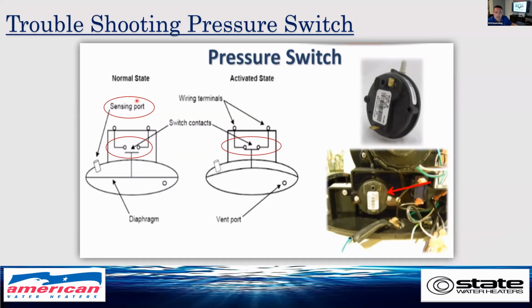So looking at this diagram, the sensing port is where the vacuum from our blower is coming and plugging into it. In a normal state, our diaphragm is flat, pulling that switch contact away. So that means we're in an open position. When the blower receives power and comes on, the vacuum is created, pulling that diaphragm up and making those contact switches go active.